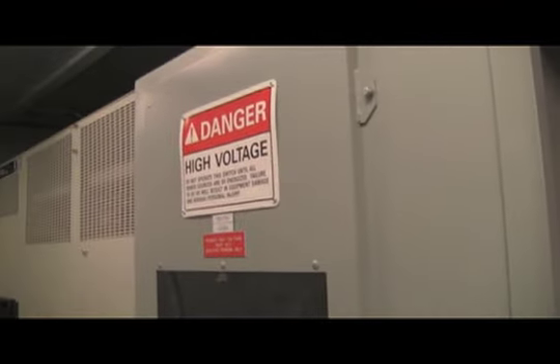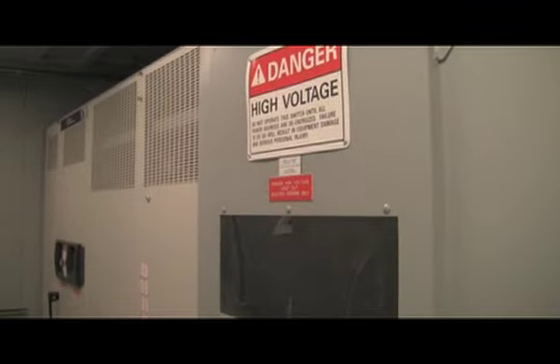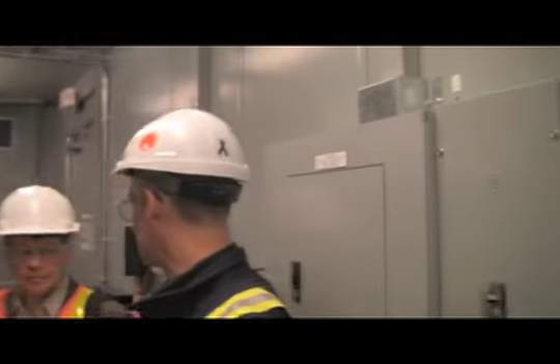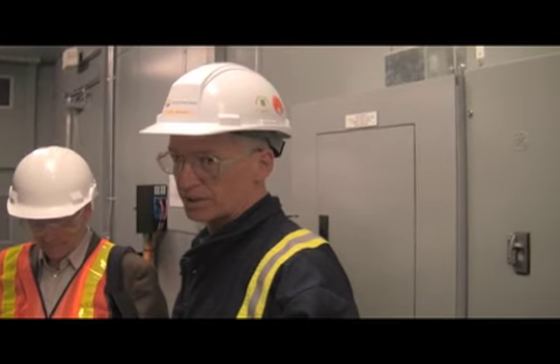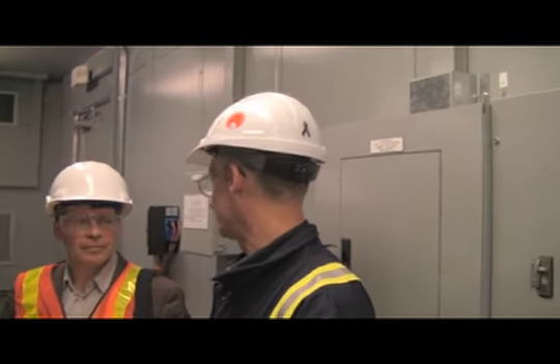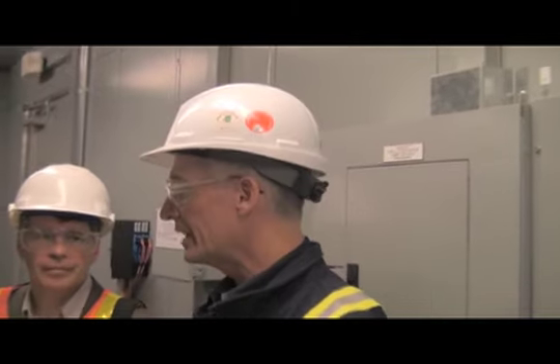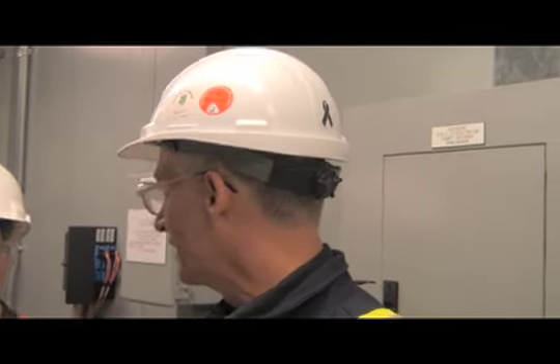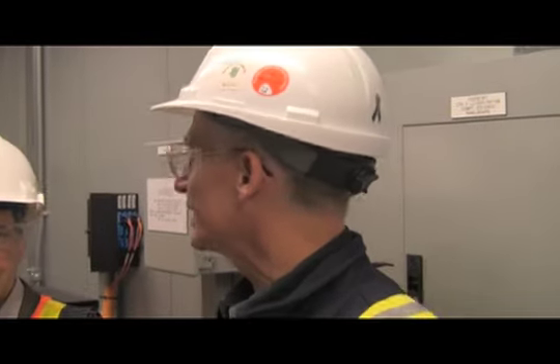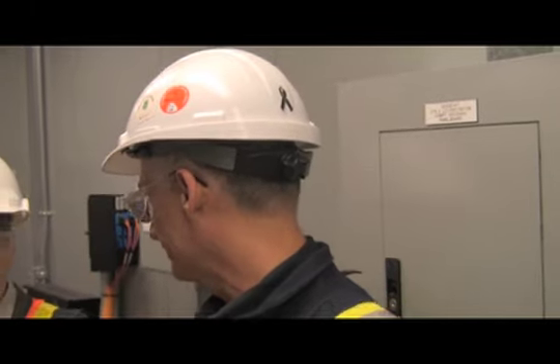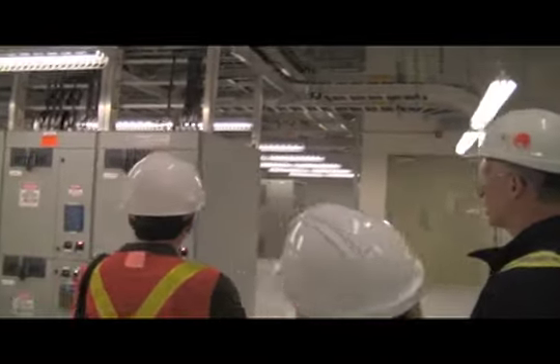The gas turbine and generator is a huge piece of equipment, and it takes a lot of force to get it going from stop. So we would have to have a pretty big motor attached to it, which would be a huge expense. So what we do for startup is convert the generator to a motor to start the gas turbine, and when it gets close to synchronous speed, it can run on its own. Then we take the switchgear out, it no longer operates as a motor, and it begins as a generator. We've got a lot of switchgear in here, and it's all organized.